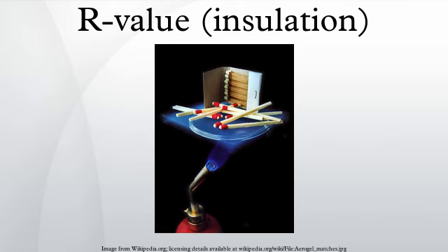The limitations of R values in evaluating radiant barriers. Unlike bulk insulators, radiant barriers resist conducted heat poorly. Materials such as reflective foil have a high thermal conductivity and would function poorly as a conductive insulator. Radiant barriers retard heat transfer by two means: by reflecting radiant energy away from its surface or by reducing the emission of radiation from its opposite side.